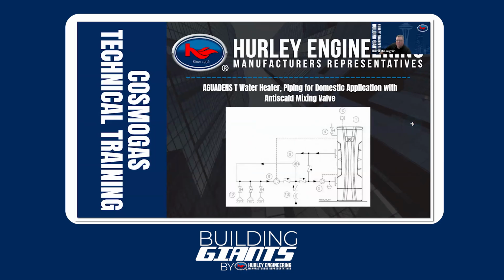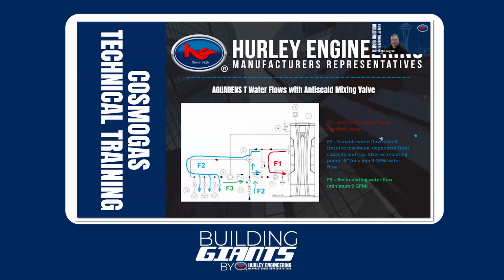Now, if I go to the next one, this is going to be a more typical, probably 80, 90, maybe even more % of your instantaneous water applications. And here, all we've done is we've added that 3-way mixing valve or that anti-scald valve, right? So when I look at the flow circuits now, I've got a third flow circuit because of that. I've still got my F1 circuit that I've got to keep the flow where I need it to be to prevent limescale buildup. I've still got circuit 2 that is going to be indicative of what my actual domestic hot water flow is in that system. But then I've also got the third flow circuit, which is just my recirculation.